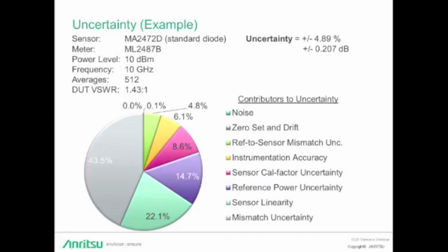It's important to note that it's typically not the sensor VSWR, but rather the DUT VSWR that dominates the uncertainty element. If your test can handle a reduction in the measurement range, adding a precision attenuator of 3 to 10 dB can actually reduce the contribution of that mismatch uncertainty 2 to 10 times. In this example, noise, zero set, and drift are basically a non-factor. However, as the measurement levels approach the lower measurement range of the sensor, these will become more significant.